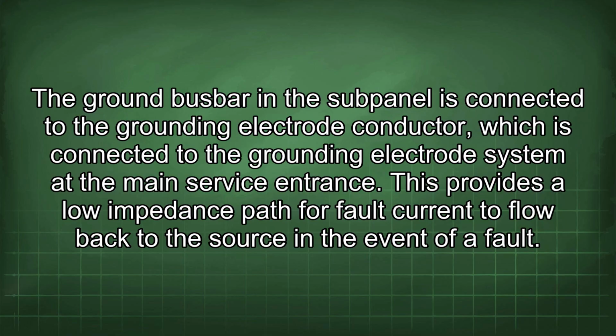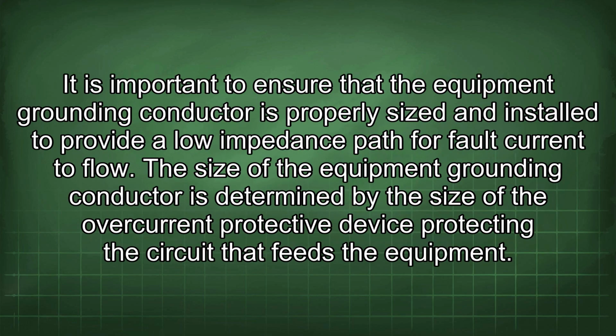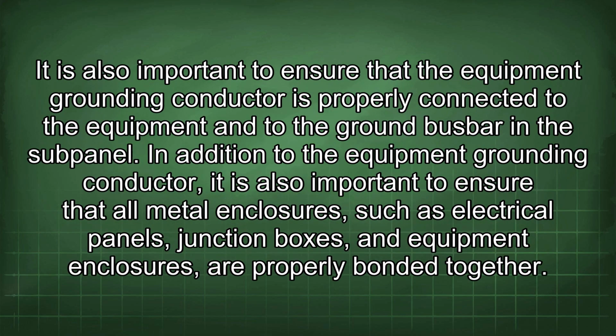This provides a low impedance path for fault current to flow back to the source in the event of a fault. It is important to ensure that the equipment grounding conductor is properly sized and installed to provide a low impedance path for fault current to flow. The size of the equipment grounding conductor is determined by the size of the overcurrent protective device protecting the circuit that feeds the equipment. It is also important to ensure that the equipment grounding conductor is properly connected to the equipment and to the ground busbar in the subpanel.